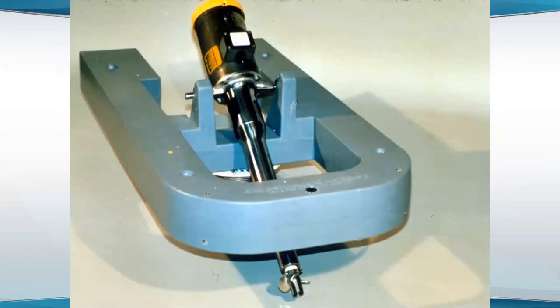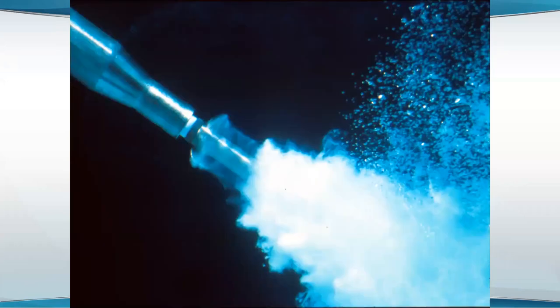The propeller aspirator pump type — this particular one is an Aire-O2 aerator — is a kind of efficient aerator. It has a rotating hollow shaft with a diffuser near the impeller. The impeller jets the water forward, and a housing around the hollow shaft has a hole near the top. Air is forced down into the shaft as the impeller evacuates it — it's an aspirator-type device, and the water comes out with very small bubbles of air in it.